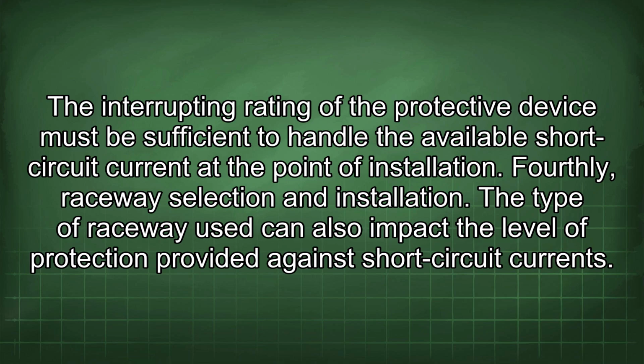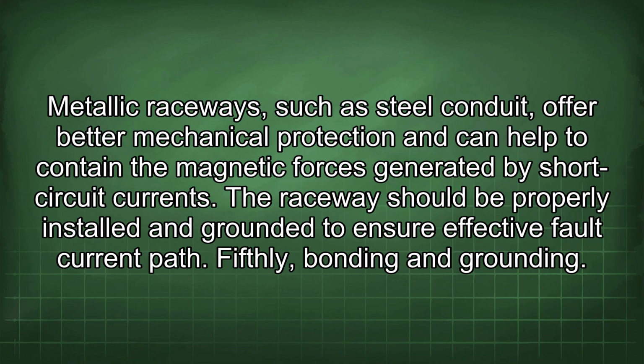Fourthly, raceway selection and installation. The type of raceway used can also impact the level of protection provided against short-circuit currents. Metallic raceways, such as steel conduit, offer better mechanical protection and can help to contain the magnetic forces generated by short-circuit currents. The raceway should be properly installed and grounded to ensure an effective fault current path.